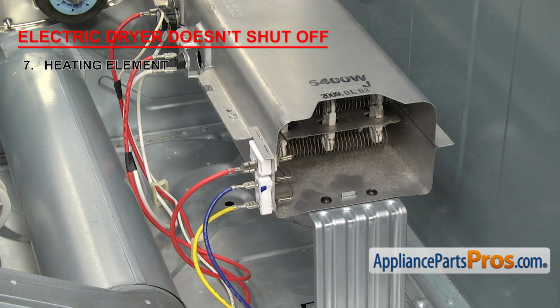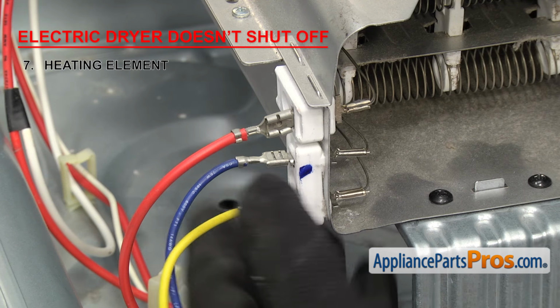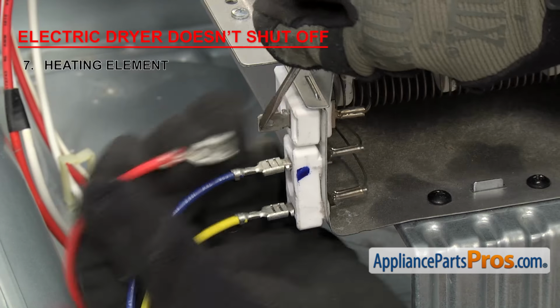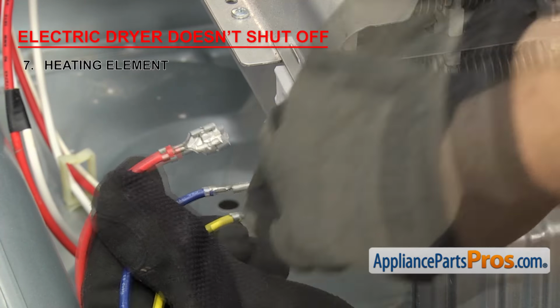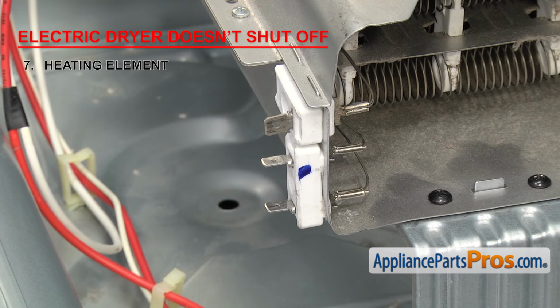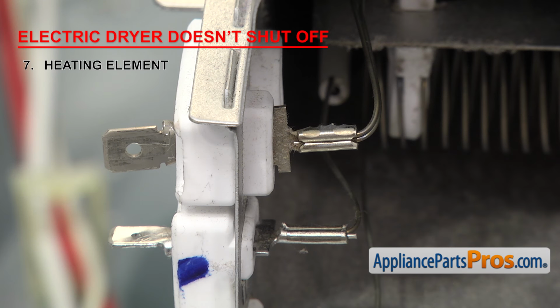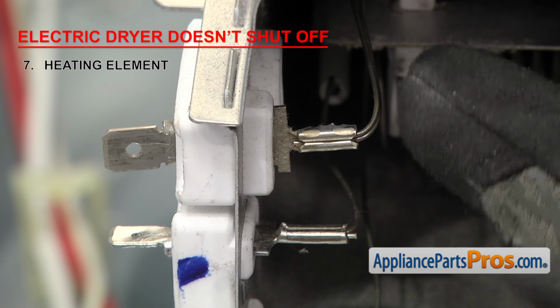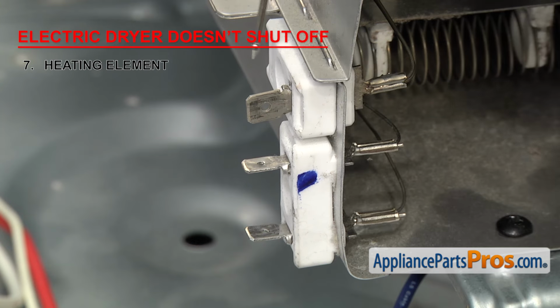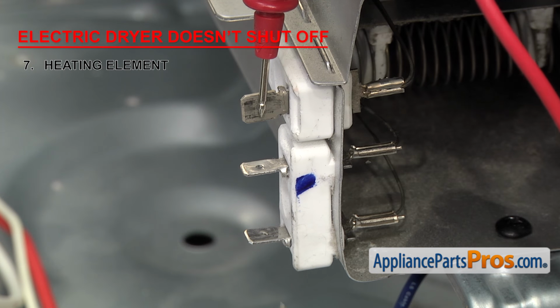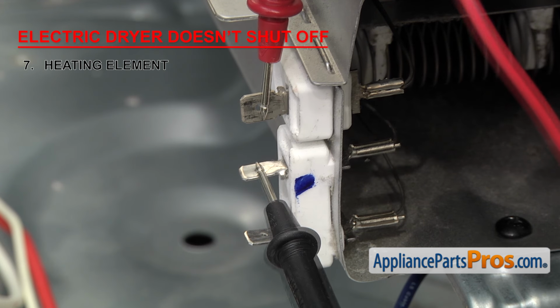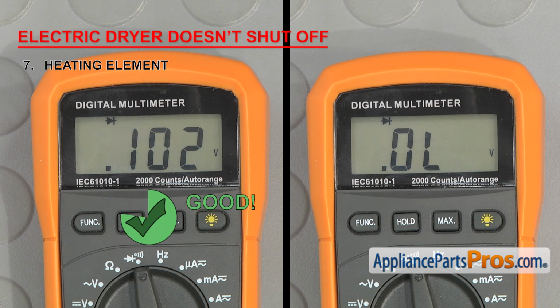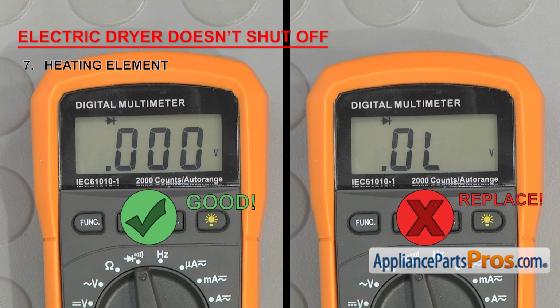To check a dual coil element, you need to remove the wires and then check each coil separately. To do that, we need to put a probe on the terminal that has 2 coil wires going into the back of it, and then we need to touch the other probe to each of the other terminals. They should both have continuity. If either one doesn't, you'll need to replace it.